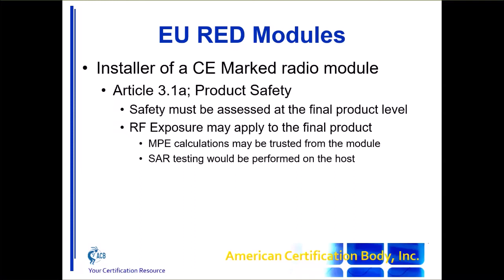So for the installer, product safety, they're going to do product safety on that final product, of course, and there's really nothing to be carried over from the module to the final product, except maybe the RF exposure if it was based on a calculation. If it's a SAR test for a portable device, then that will always be done on the final installation.